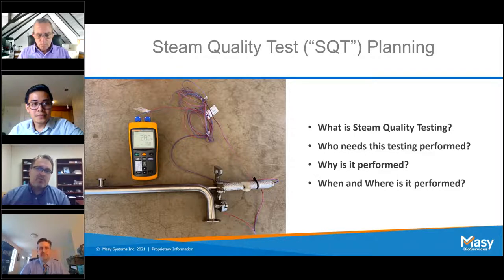Certainly, Rob. Steam quality testing is a process of evaluating the physical properties of the steam to make sure that it is appropriately supporting the sterilization process it's being used for. When we perform a steam quality test, there are three characteristics that we're testing or measuring. The first is non-condensable gases. What we're looking for is gases other than water in the steam supply. Typically that's atmospheric air, the things that make up our air: oxygen, carbon dioxide, et cetera. We don't want those things in the steam. At greater amounts, they will limit the effectiveness of the steam in providing lethality.